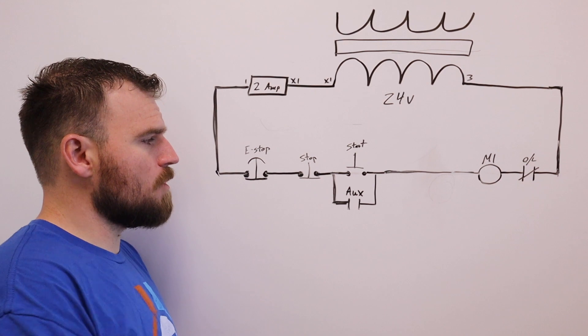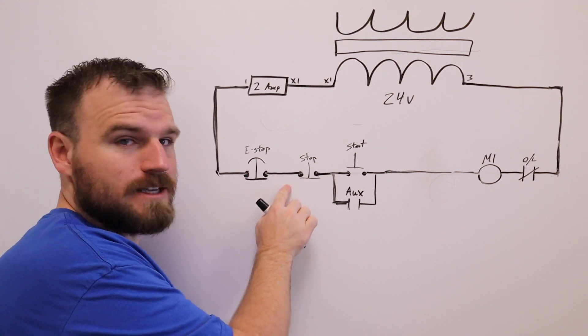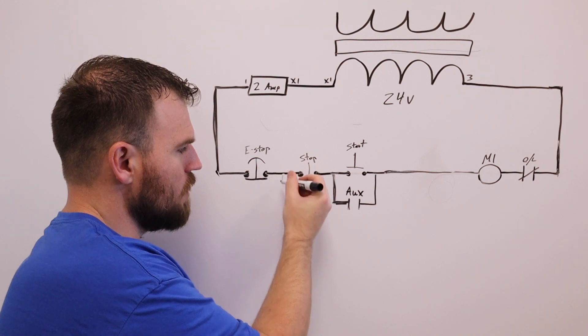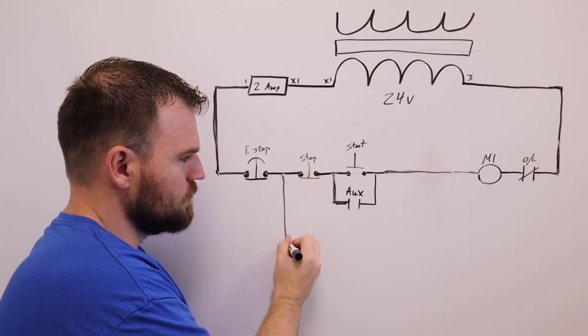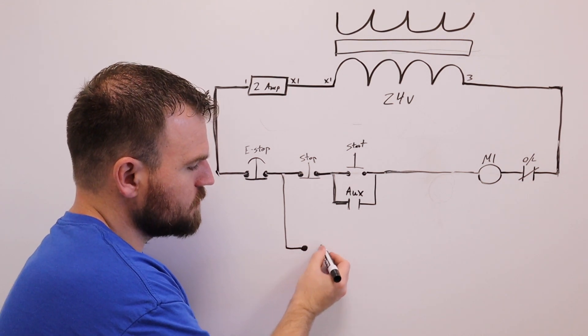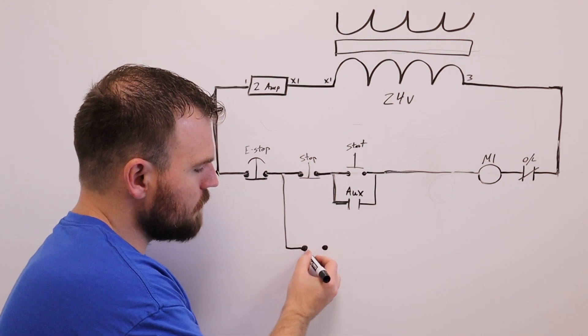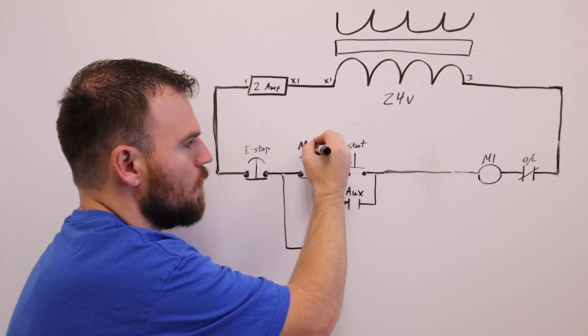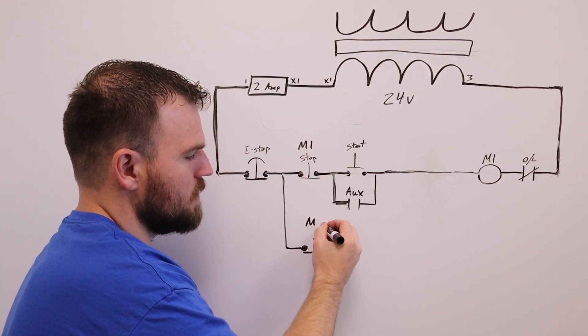Right here we have our e-stop. What we're going to do after the e-stop is start putting in another rung, another drop down to about right here. It's going to come over and go into another stop switch. So this stop switch will stop motor one - we'll do M1 stop, and this will be M2 stop.